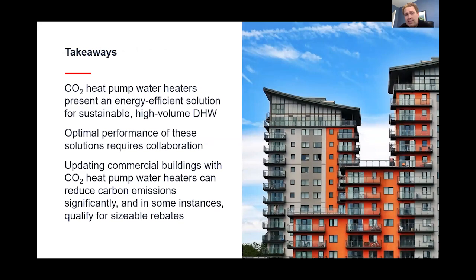So really, this is the last slide here. The takeaways. The CO2 heat pump water heaters present an energy efficient solution for sustainable high volume domestic hot water. Optimal performance for these requires collaboration with the manufacturers. These products are different, like Matt mentioned, than the old boilers. So you're gonna have to work with the manufacturers to ensure it's proper. And then updating commercial buildings with CO2 heat pump water heaters can really reduce carbon emissions significantly, and in some instances qualify for sizable rebates.